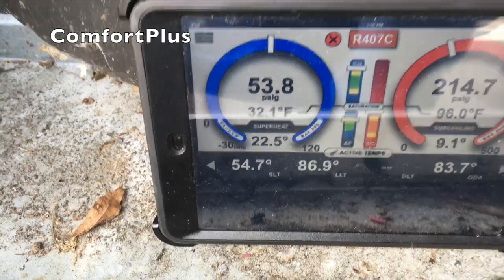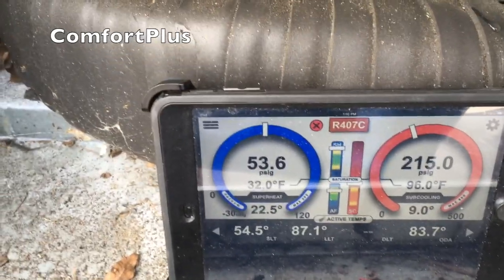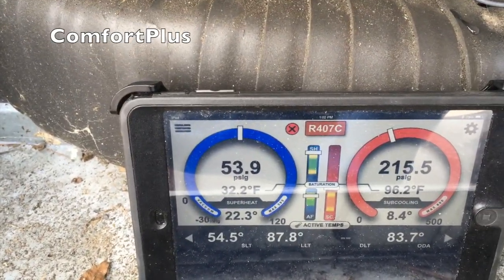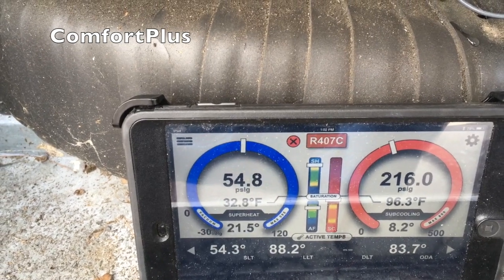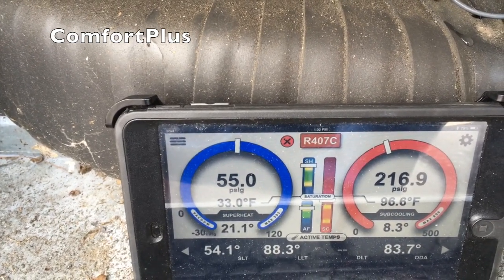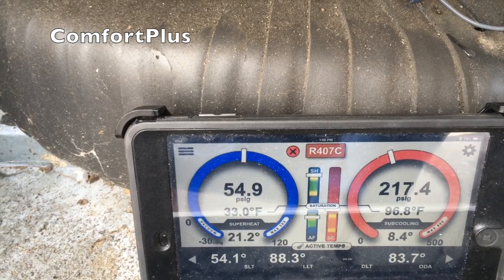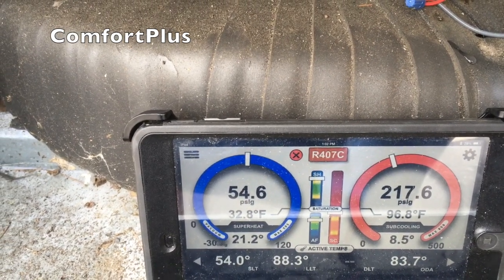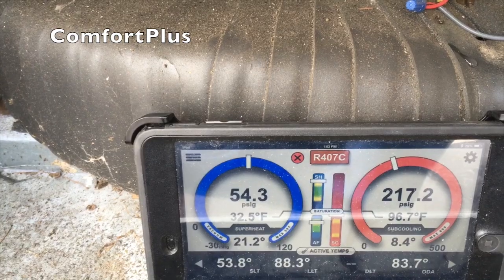She just came back on. We actually raised the set point to 54 degrees, so it came back on. It's got a 5-degree differential. It came back on at 59 degrees. And the superheat's pulling back down. It's going to pull down below 20 here pretty quick probably.